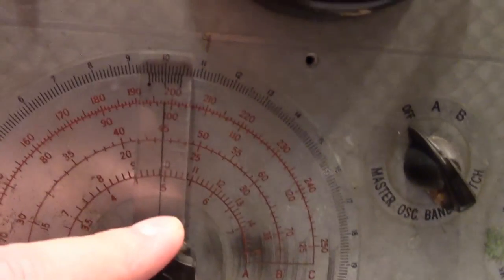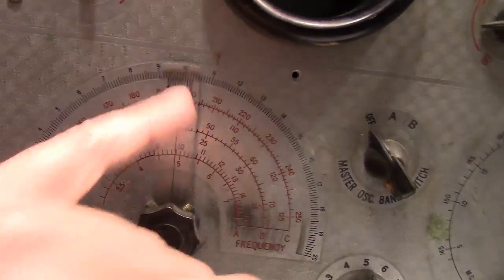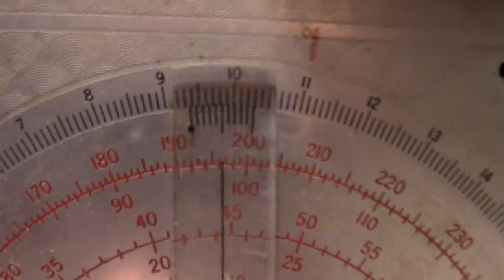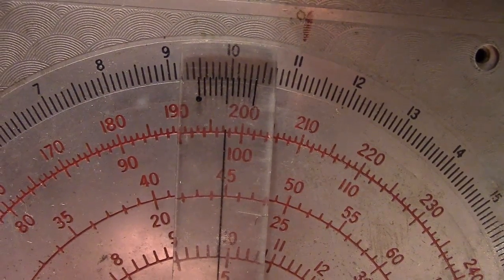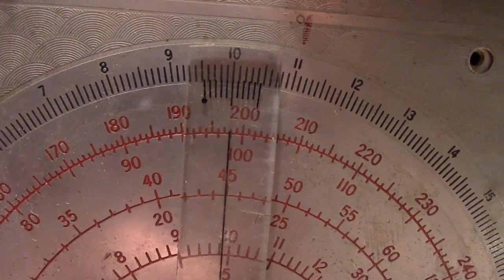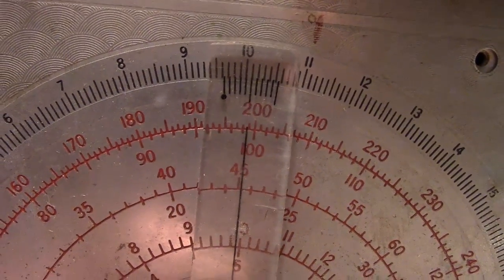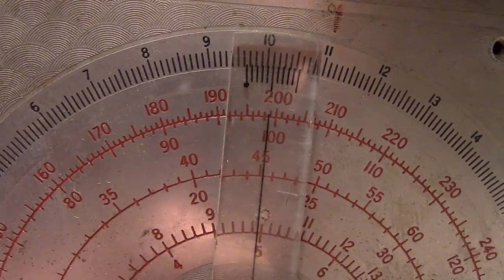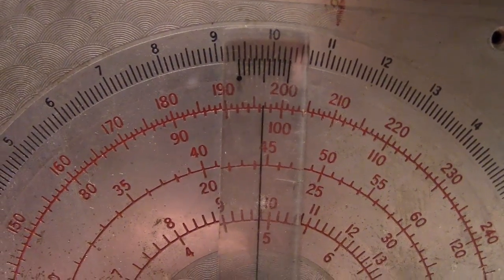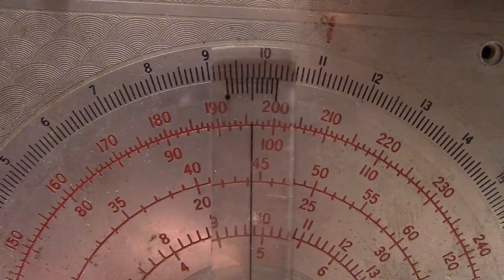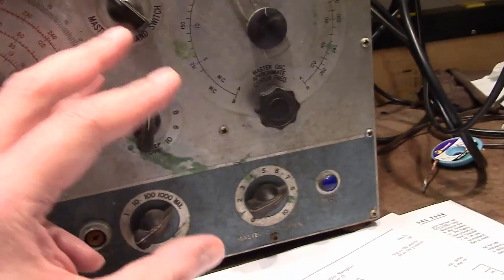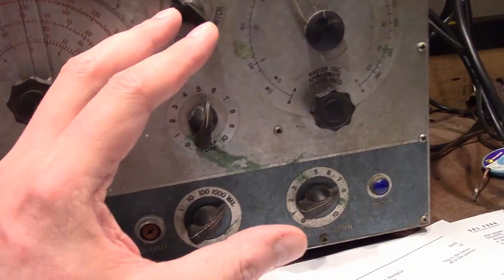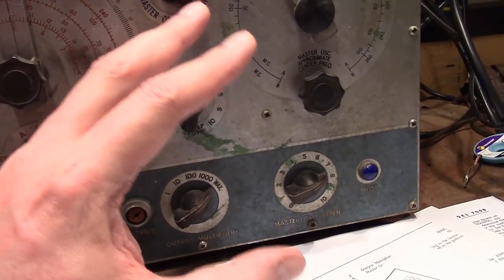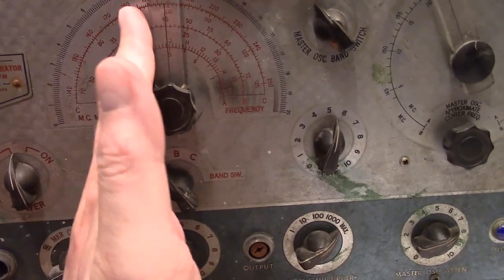The dial on this marker generator is kind of nifty. In addition to your usual ranges and marks for frequency here, there's also some marks on the pointer as well. And there's a technique they outline in the manual for using this to interpolate or compensate for calibration errors. Because this is really the key as a marker generator. As long as you can sweep some RF, even if it's not perfectly linear, as long as you have a good marker, you can find where you're at.